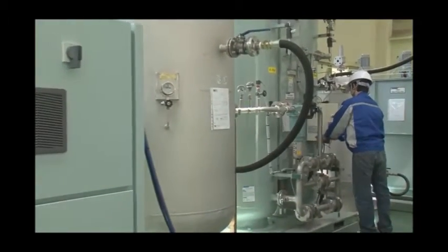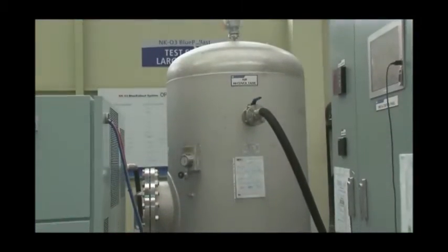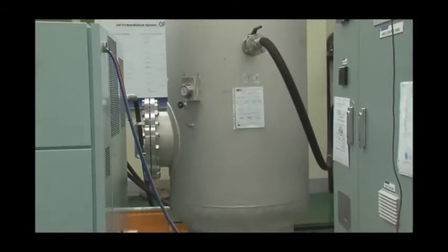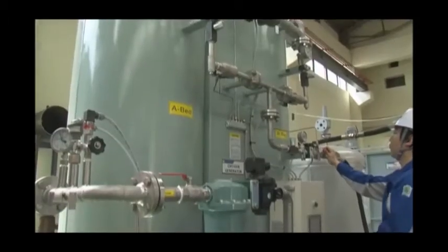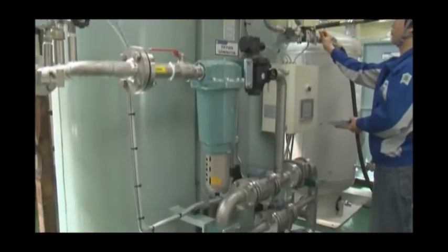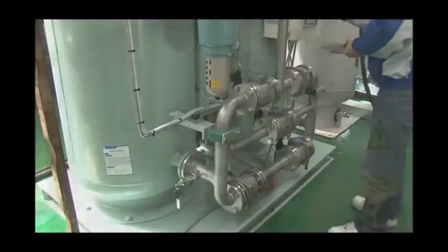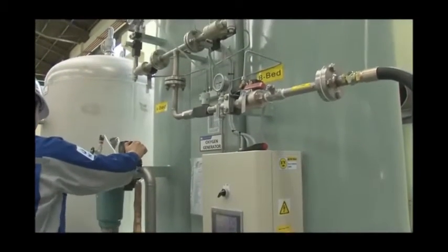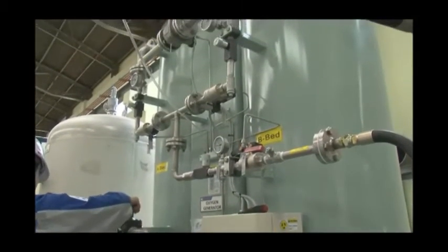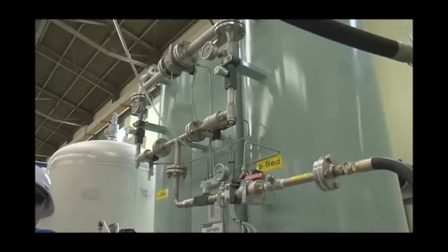This oxygen generator is PSA, pressure swing adsorption type, having two vessel beds filled with molecular sieves by which nitrogen is vented out and only oxygen passes through the vessels and directed to the oxygen receiver.